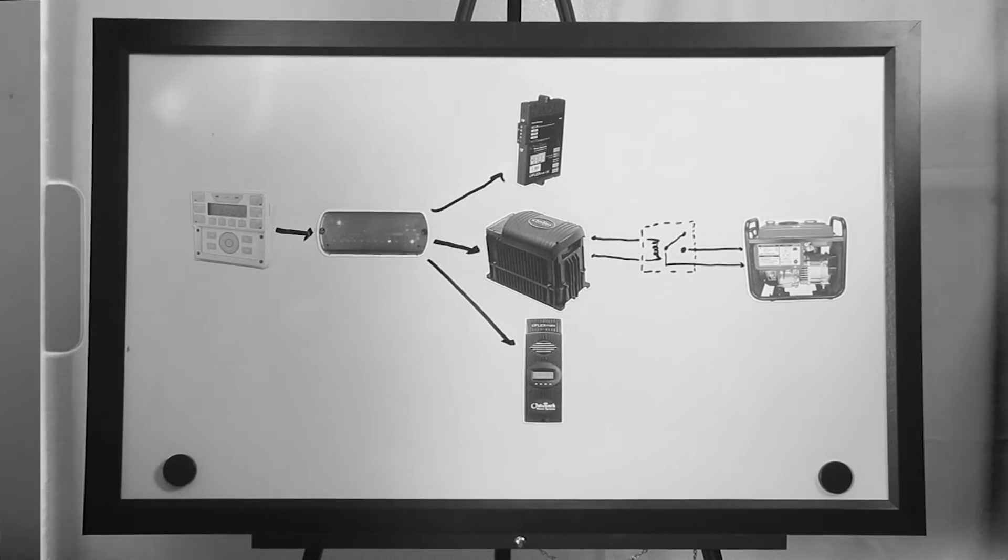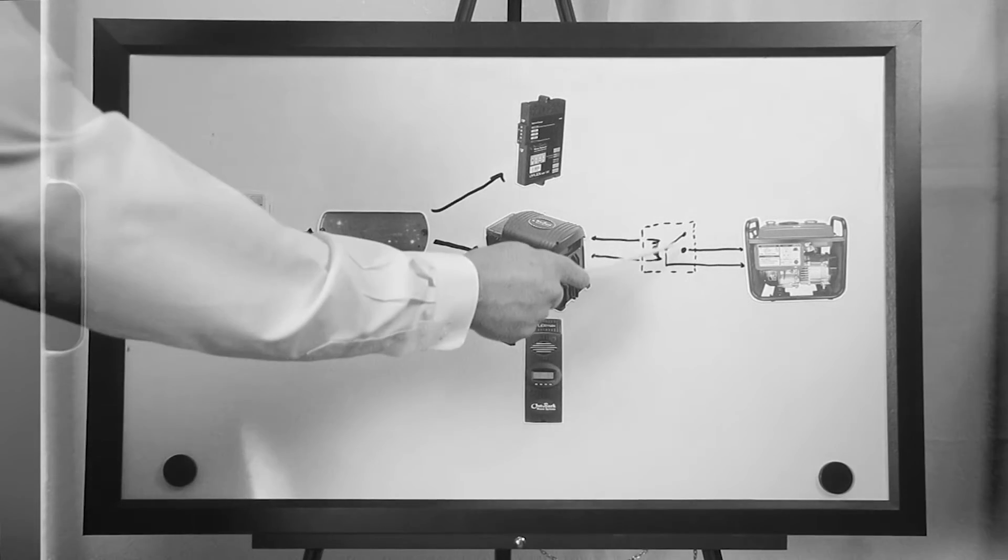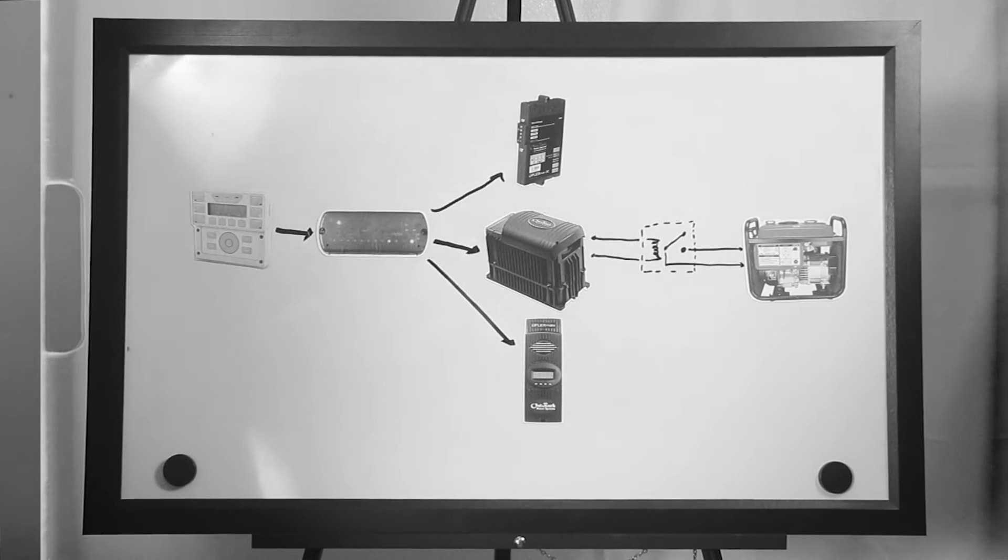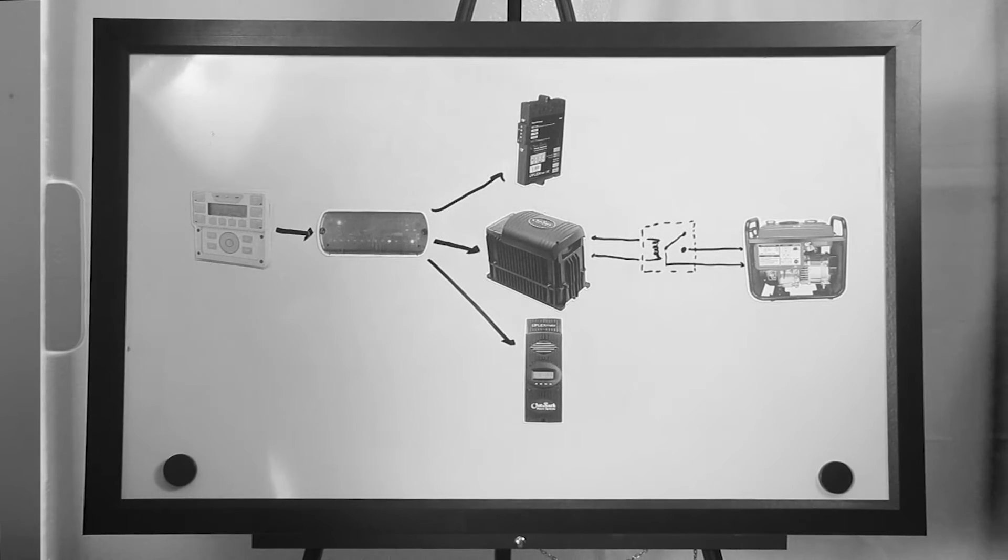Once the relay gets the 12-volt signal, we close the relay contacts, creating a short circuit to the generator sense wires, which causes it to start.